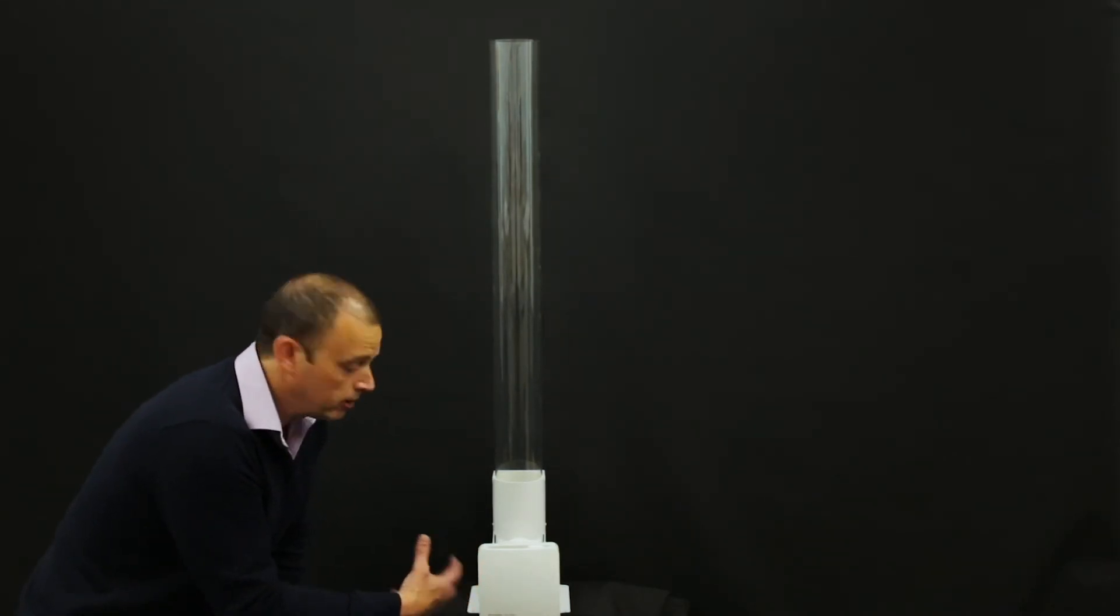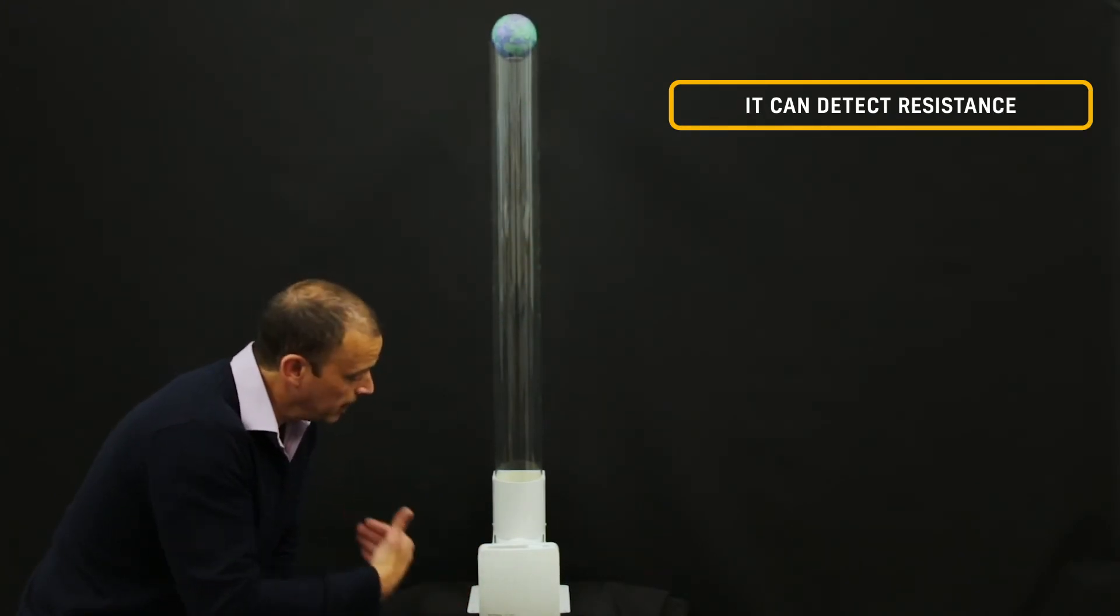It's quite an intelligent fan. It's what we call a constant-volume fan, so it's detected that resistance on the system and it's automatically speeding itself up to cope with that, which is a really good feature.